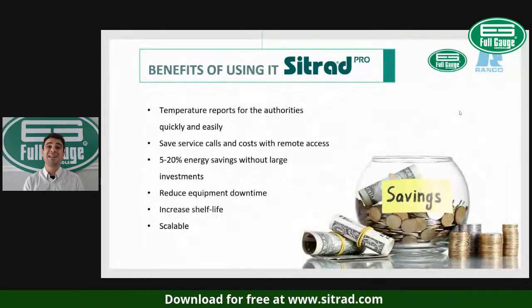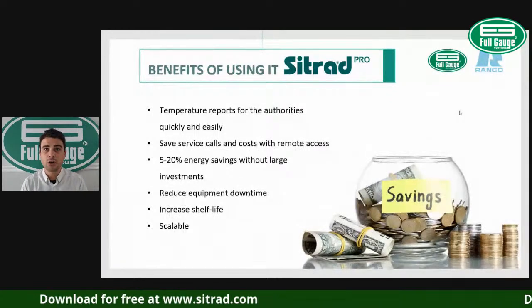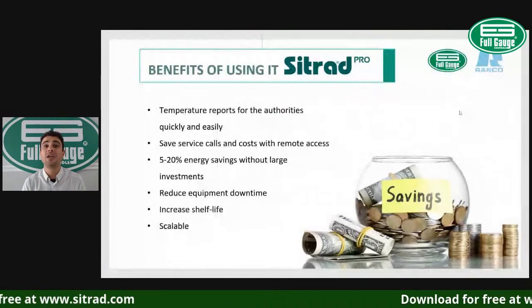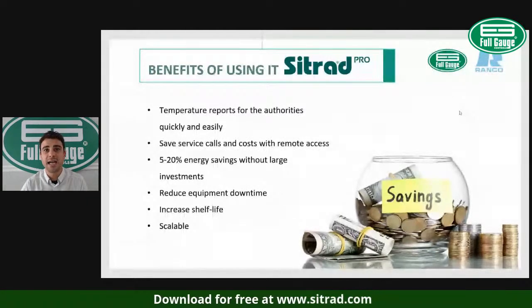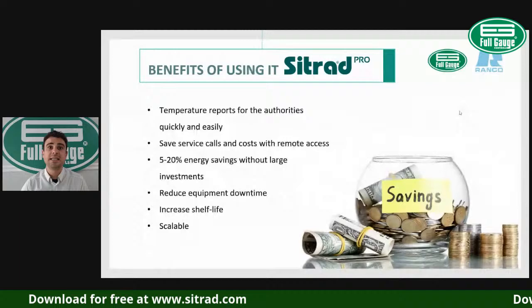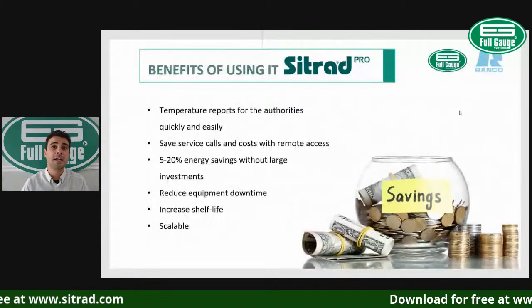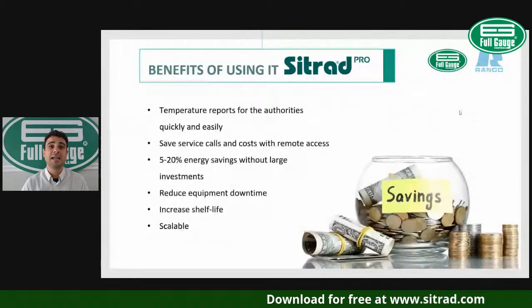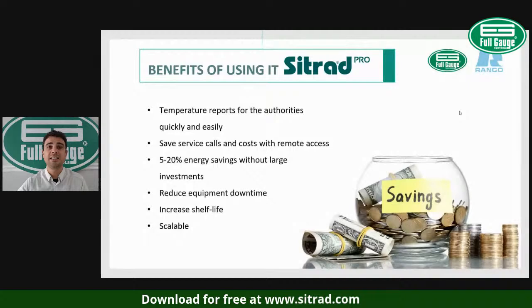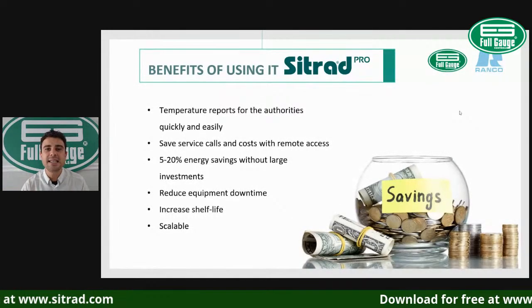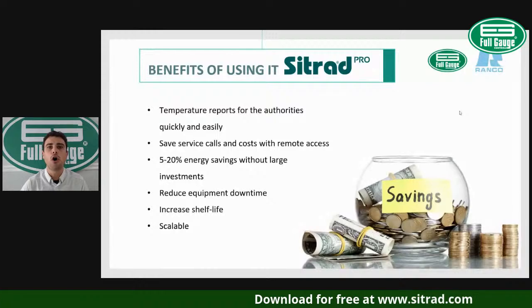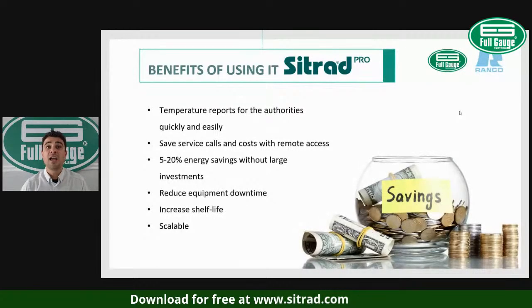Well, if you had Sitrad installed at that site, you could easily prevent that unnecessary travel, because first of all, Sitrad would send you an open door alarm. In addition to that, you could take the temperature chart report and easily identify that your coil was blocked with ice.